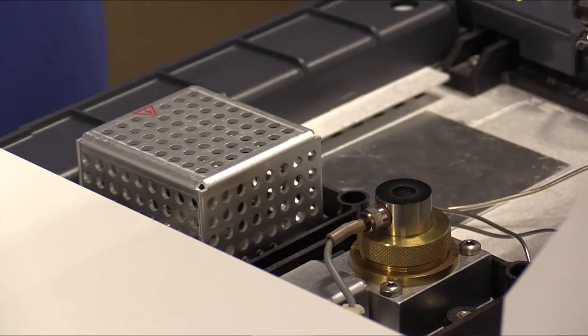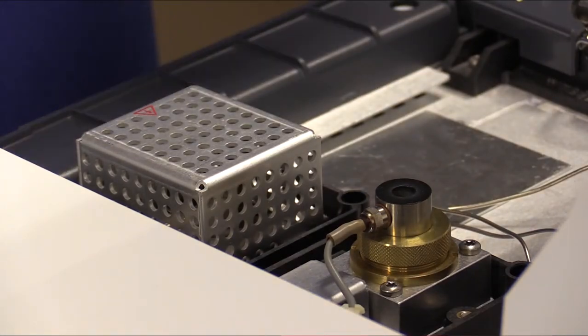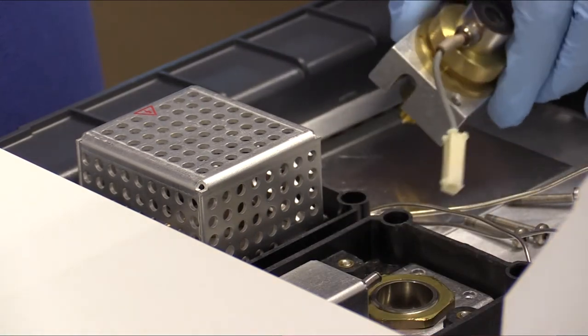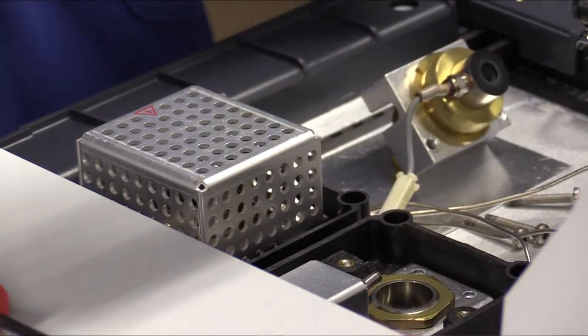we can then remove the screws that attach the FID assembly to the instrument itself. We can remove that whole assembly as one part, and that reveals to us the FID jet.